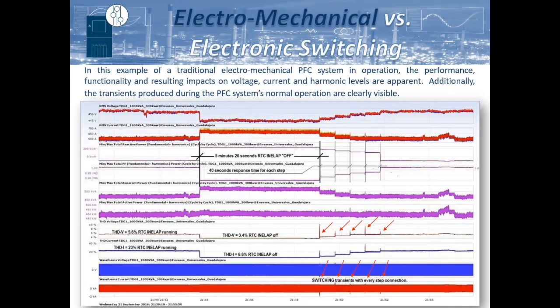So when we're talking about traditional power factor correction, and this is what's typically seen out in the field, these use electromechanical contactors to account for the reactive load demands. In general, the purpose is just to mitigate power factor penalties, right? The utility doesn't look kindly upon a facility that's not using the energy within the facility efficiently. So in order to offset the cost of correcting for that on the utility side, they might induce a power factor penalty. A traditional system works by switching in groups through the use of an electrical contactor, so it brings in all three phases all at once.